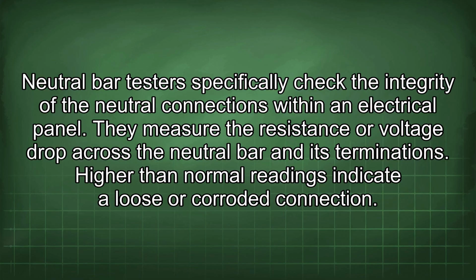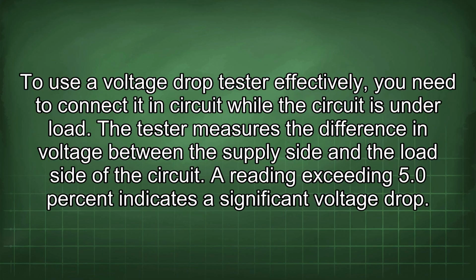Neutral bar testers specifically check the integrity of the neutral connections within an electrical panel. They measure the resistance or voltage drop across the neutral bar and its terminations. Higher than normal readings indicate a loose or corroded connection. To use a voltage drop tester effectively, you need to connect it in circuit while the circuit is under load. The tester measures the difference in voltage between the supply side and the load side of the circuit. A reading exceeding 5.0% indicates a significant voltage drop.